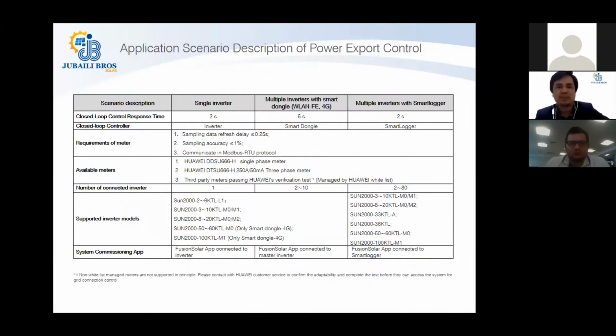Application scenario description of power export control. With a single phase inverter, it will take only 2 seconds from the point where the control is required. Let's suppose the power is going towards the grid and you want to control it from the point the power meter reads that there is extra power going towards the grid. You need to control that until the inverter receives the command and responds. The whole process takes around 2 seconds. I'll have another slide next where I will show you in a graph exactly how the inverter responds.